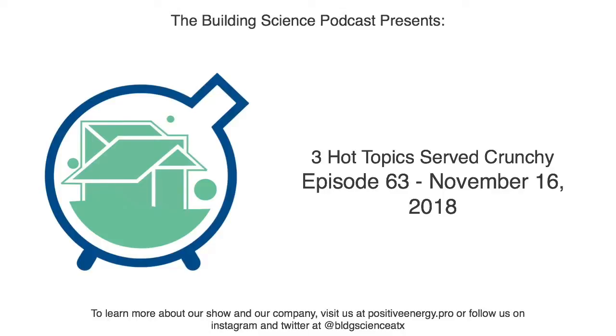Yeah, so the metric that we like to look at is watts per CFM or CFM per watt, depending on how you like to look at it. We want to see systems that are 2 CFM per watt or greater, or flipping that, taking the inverse, 0.5 watts per CFM or less. And the RenewAir units that we use are right around 0.5 when we're using them at their full rated flow. Those machines, unfortunately, are just single speed. So if we have a smaller house that only needs 50 or 60 CFM, we have to use a damper to reduce the flow. So the power input stays the same.